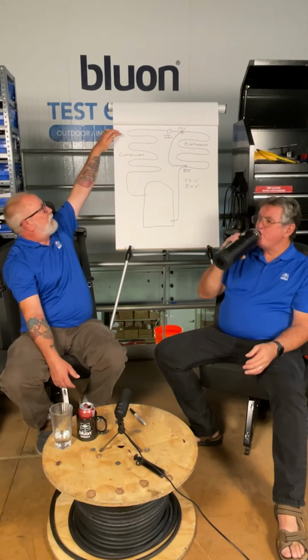Here's another thing too. If you slightly overcharge something with an active metering device, it's a lot more forgiving because you'll just stack the refrigerant in the liquid line. So stacking the condenser means at 10 degrees of subcool, you had one pipe full of liquid. If we went to 12 degrees, we had 2 pipes of liquid, which means we're stacking the condenser. When you are looking at a condenser coil, the discharge pipe of the compressor goes into the top of that coil. As it cools, down at the bottom is the liquid. So when we say stacking, it's literally stacking tubes, if that makes it easier for you to understand.